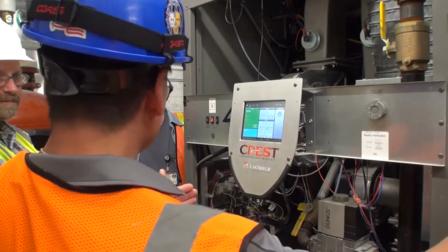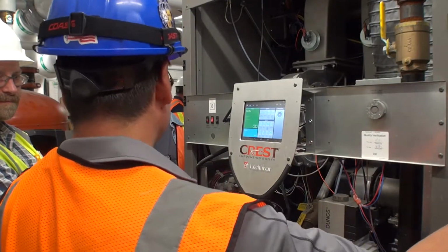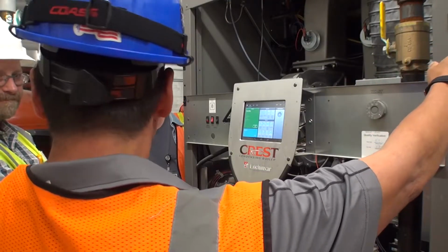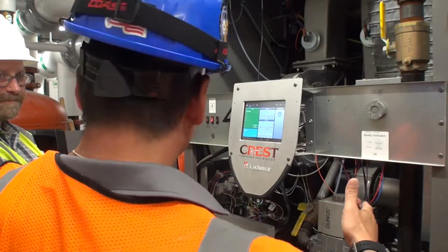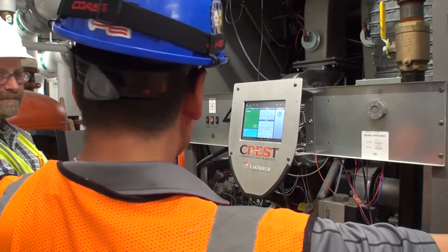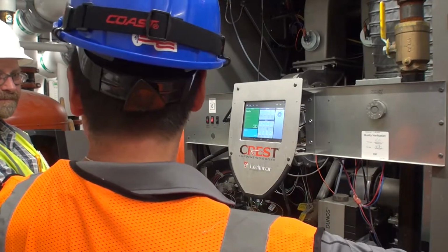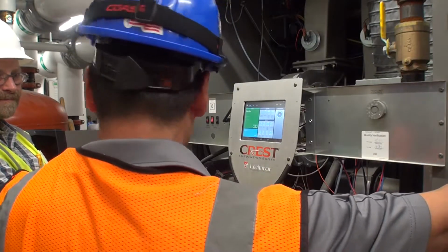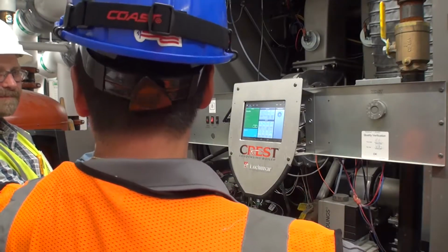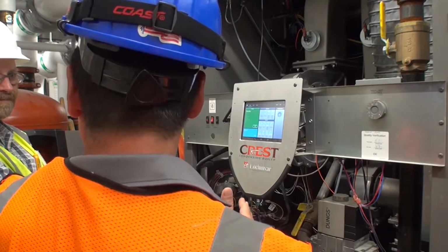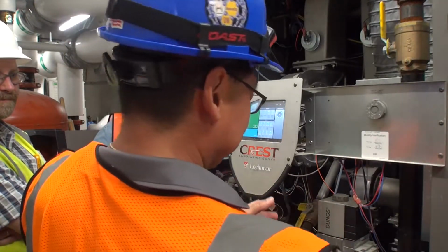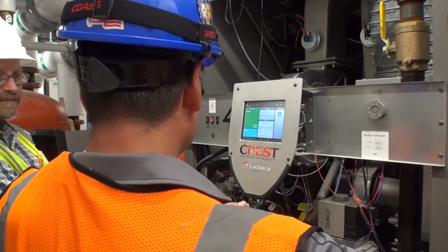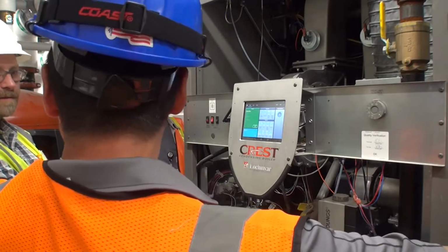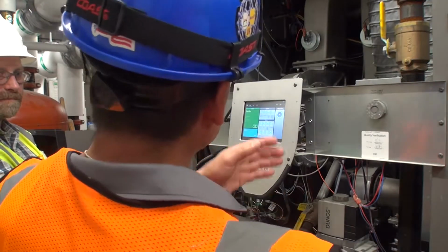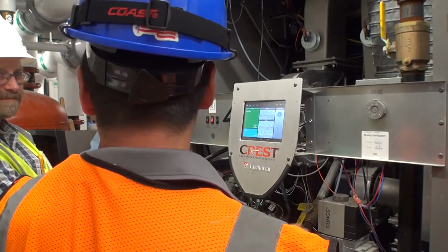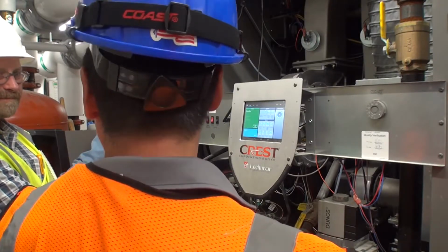The pumps are looking at your differential pressure switch, or differential pressure transmitter, in the system. So if you put a valve in between the pump and that sensor, it can't sense that. The sensor is going to go to zero. There's no differential, so it's going to try and pump. It's going to go wide open, pushing out against the boiler. So if you had the boiler, the pumps, and your sensor, who cares what the boilers did, as long as the pumps can see their sensor, they know what to do. The pumps and the boilers are not interlocked in most controls, in 99.9% of applications. They can be, but they're not.